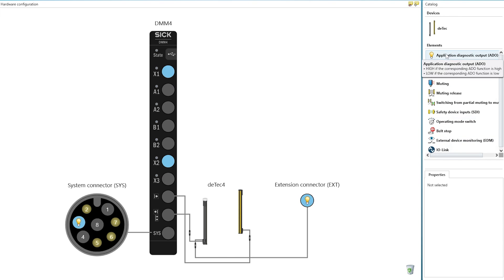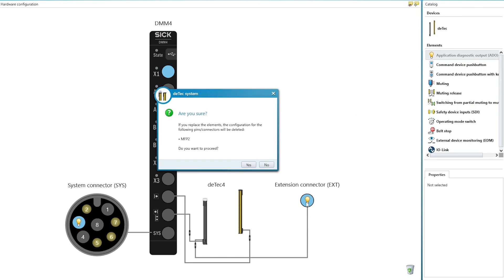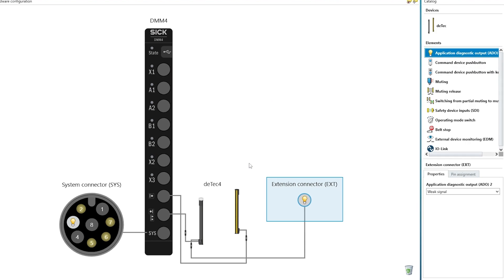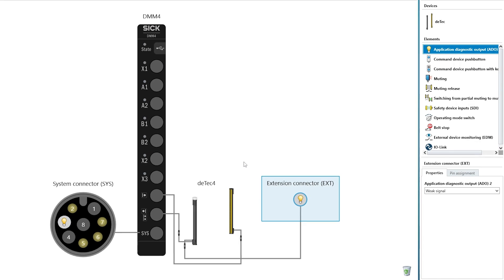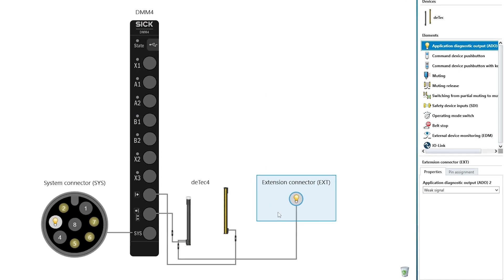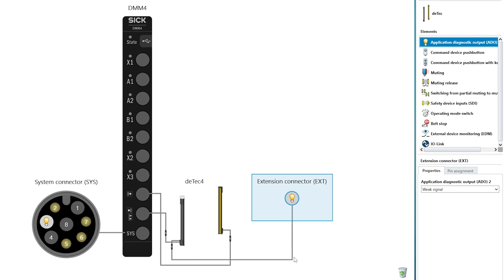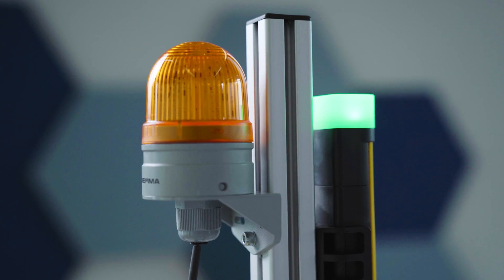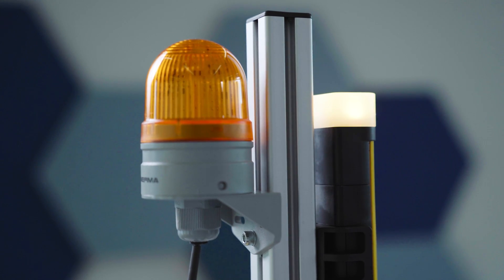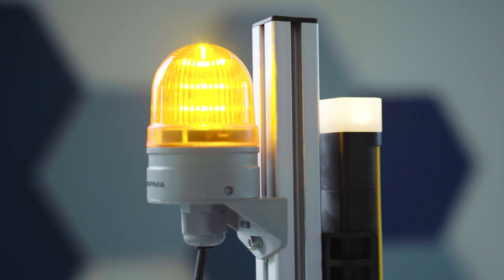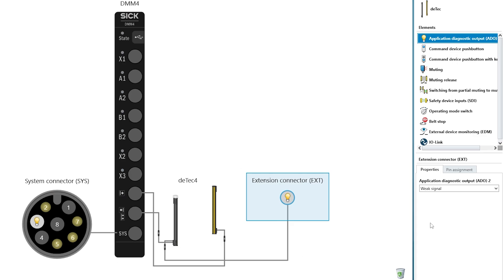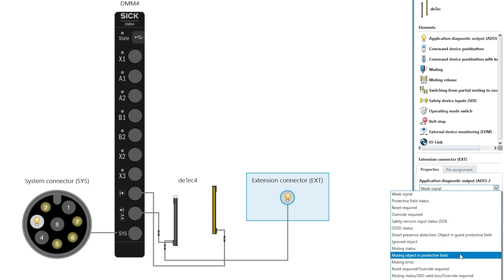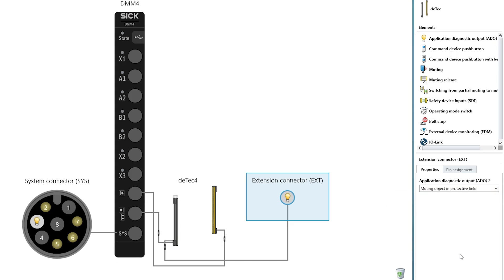Starting with the Application Diagnostic Output or ADO for short, you can see four different possibilities to connect ADO devices. In this case, you use the extension connector of the deTec4 receiver system plug to connect an external muting lamp. In the lower right corner, you can check the properties and determine the behavior of the lamp. Muting object in protective field.